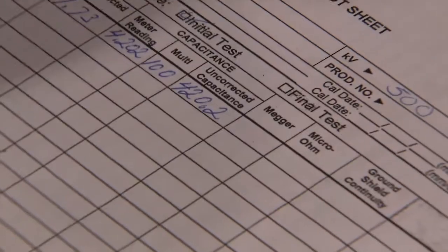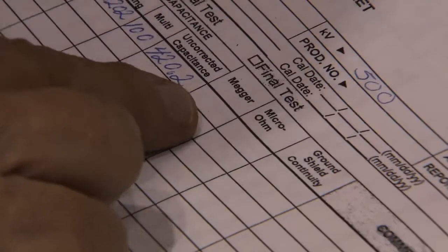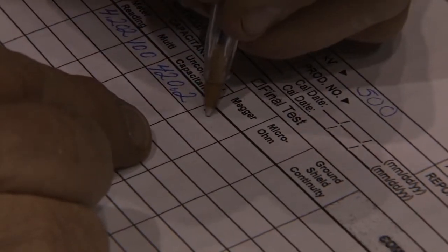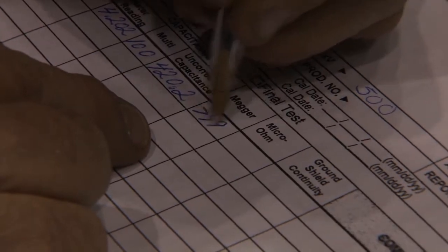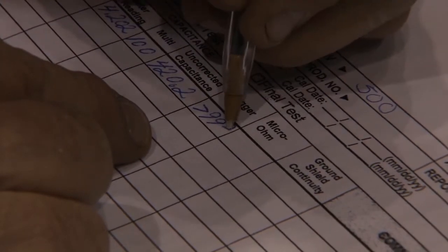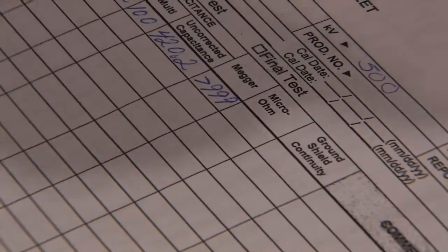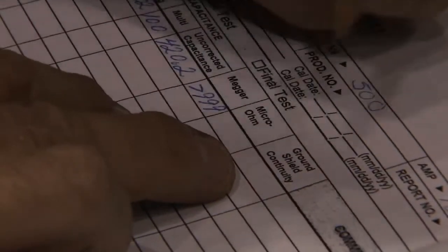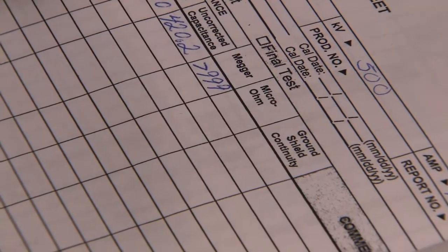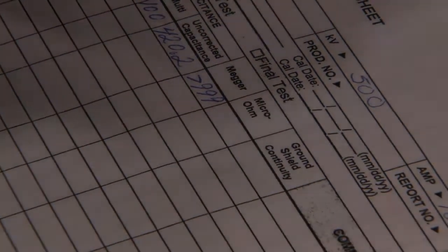Okay. And the Megger, we already did that Megger test. Yes, we record that as well, and that was greater than 999. On this one here, they ask about a ground shield continuity test. That's for a different type of bushing. It's not applicable to this one, so we do mark it off as NA, not applicable.